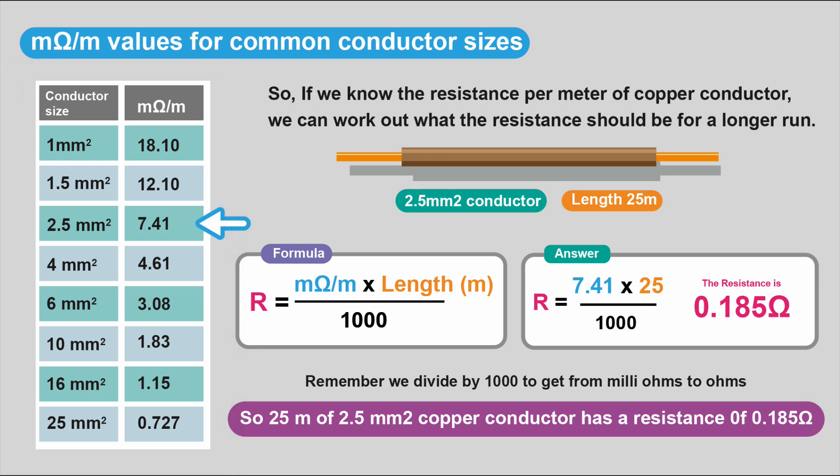So we can work out what the resistance should be for a given length, and it's some simple math. The resistance will be the milli-ohms per meter times the length in meters divided by 1,000. Remember, we divide by 1,000 to get it back into ohms from milli-ohms.